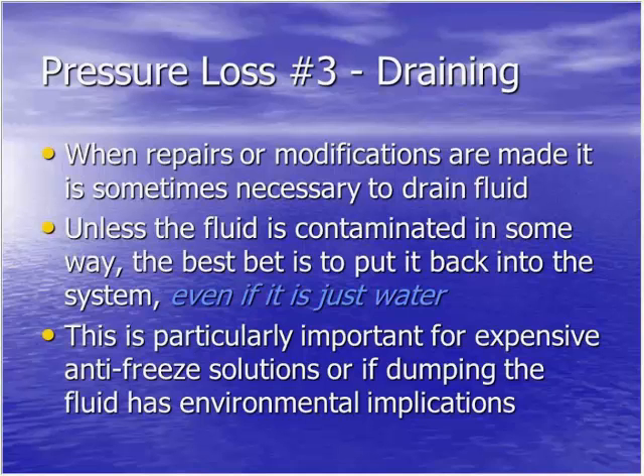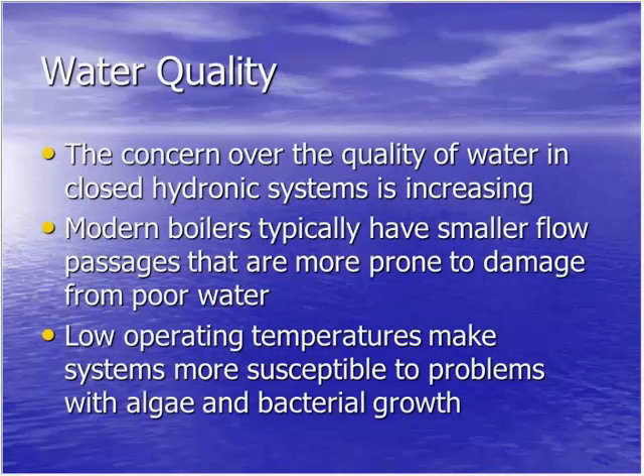Water quality. The concern over the quality of water in closed hydronic systems is increasing. These modern boilers typically have smaller flow passages that are more prone to damage from poor quality water. The water that comes out of the tap, essentially what you get, there's chlorides in it, calcium that can scale. There's all types of things in the water that aren't necessarily good for the hydronic system. There's been several other presentations I've seen recently, here and in other places, about the use of demineralized water, promoting the use of good quality water that doesn't have a lot of those salts and minerals in it. Low operating temperatures also make systems more susceptible to bacteria and algae growth as well.